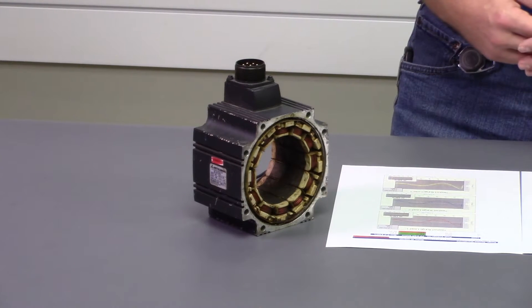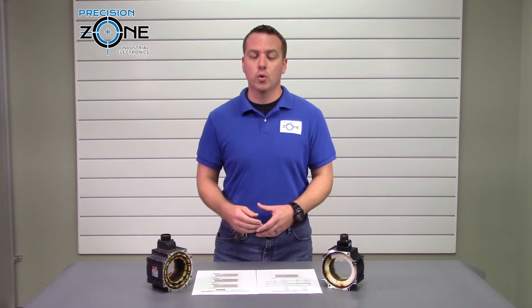These analyzers are used by quality motor winding shops and OEMs to verify that stators have been wound correctly. Here's a great example of how a surge test can detect a turn-to-turn short in a winding.